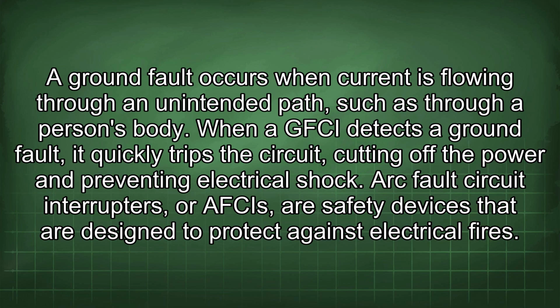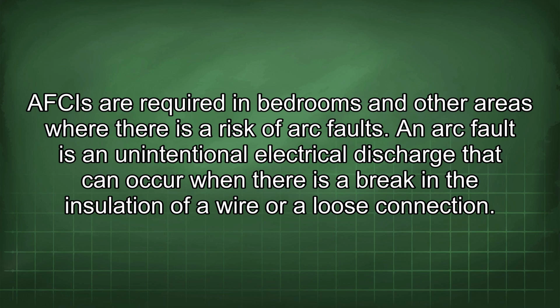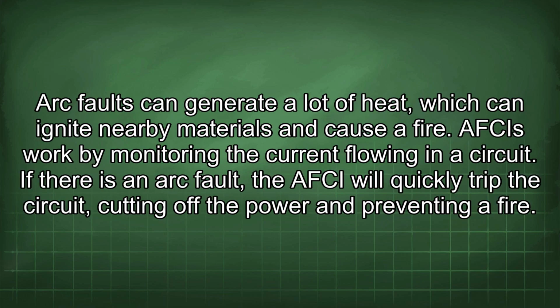Arc fault circuit interrupters, or AFCIs, are safety devices that are designed to protect against electrical fires. AFCIs are required in bedrooms and other areas where there is a risk of arc faults. An arc fault is an unintentional electrical discharge that can occur when there is a break in the insulation of a wire or a loose connection. Arc faults can generate a lot of heat, which can ignite nearby materials and cause a fire. AFCIs work by monitoring the current flowing in a circuit. If there is an arc fault, the AFCI will quickly trip the circuit, cutting off the power and preventing a fire.